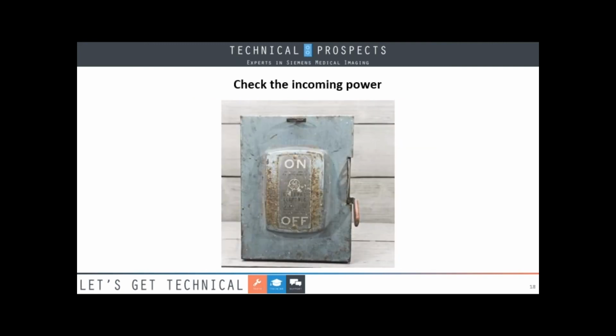All right. If you don't see, hear, or smell anything unusual, it's time to look at power. This is something odd, but I've actually found in medical equipment, it's happened. The incoming cables will vibrate, so they'll get a little loose, and you'll have issues you won't even see. So if I'm going to measure power, I'm going to turn that breaker off, go in and tighten the cables. Then I'm going to turn it back on, and measure incoming and outgoing power.